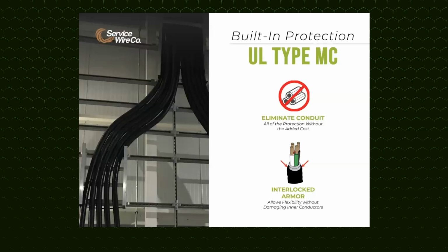It is suitable for wet and outdoor applications or direct burial underground or in concrete. With such built-in durability, jacketed MC is a great fit for EV charging stations. Service Wire can manufacture to your exact specification, including oversized grounds. This cable is available 14 gauge through 750 MCM, 2 to 37 conductors in XHHW-2, and 6 gauge through 750 MCM, 3 or 4 conductors in RHW-2. Inner conductors are insulated with thermoset insulation and available in 120 volt and 480 volt color codes, numbered or striped for easy phase identification.